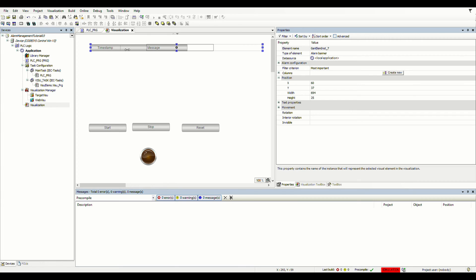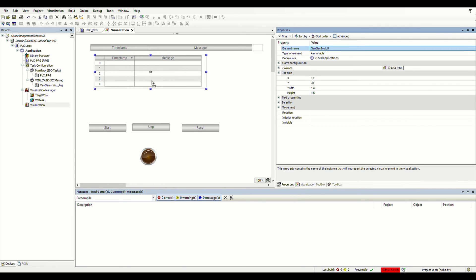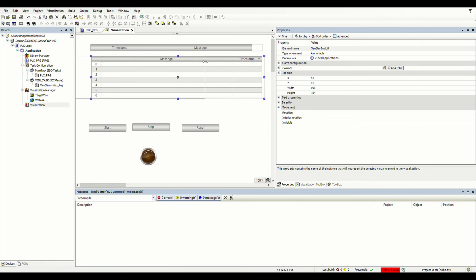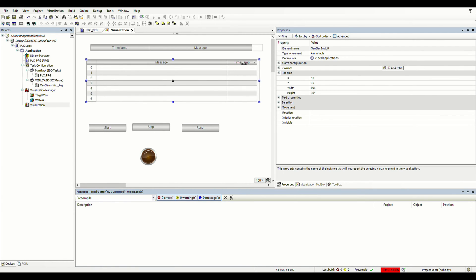One element is the alarm banner — it shows only a single alarm at a time, used to display the most recent alarm. We also have the alarm table, which is used to display more than a single alarm. We may have several alarms happening at the same time, and in the table we can show them simultaneously. We need to configure some settings for these elements, which I'll go through in the coming minutes. This will be the type of visualization we have.